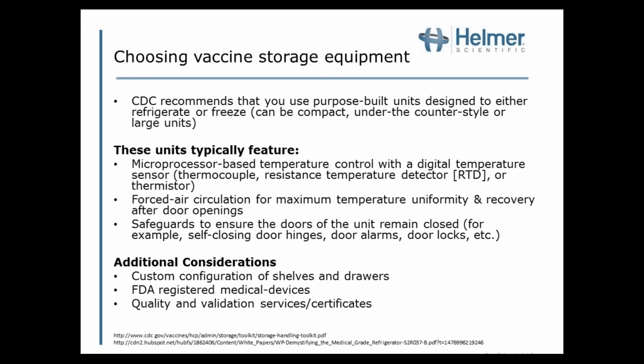Some manufacturers are registered with the FDA, registering their refrigerators as medical devices. One nice benefit is that it subjects them to additional regulation in the manufacturing process and to FDA inspections of the facility. It's an extra quality control, and I think it says something about a manufacturer willing to go that extra mile despite it not being required — they want to stand out and show you how they're designing and building their units.